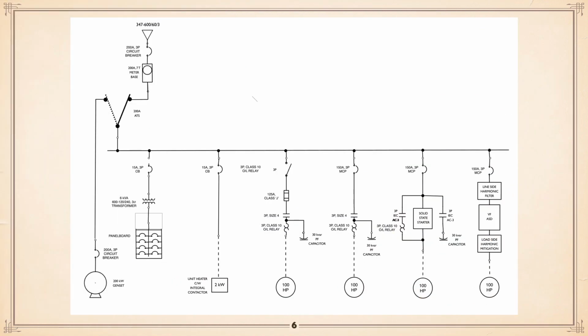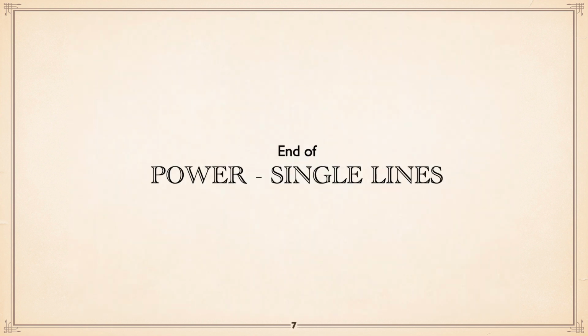And there's the arrangement with a standby generator, an automatic transfer switch, whereby normally everything's powered off the utility, just the same drawing we had before. In an emergency, if the utility fails, the genset fires up, the genset has a feeder breaker, and that then feeds through the transfer switch, and everything will be powered off that. And that, believe it or not, is the end of that section.